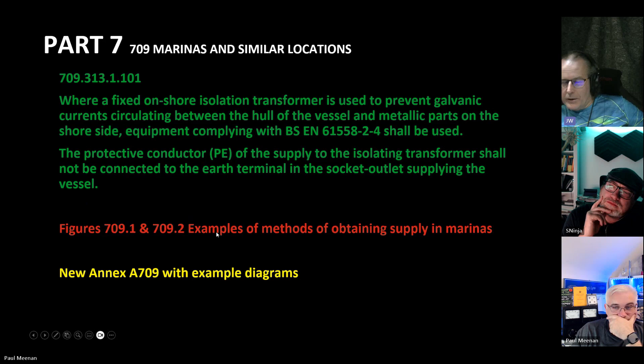709.313.1.101, which is where a fixed onshore isolation transformer is used to prevent galvanic current circulating between the hull of the vessel and metallic parts on the shore side. Equipment complying with BS EN 61558-2-4 shall be used, and the protective conductor of the supply to the isolated transformer shall not be connected to the earth terminal in the socket outlet supplying the vessel. It should be pretty obvious, because if you've got an isolated transformer, the whole point is you don't want to connect it to the protective conductor of the supply, because otherwise it's not an isolated transformer anymore. So yeah, fairly common sense stuff, really.